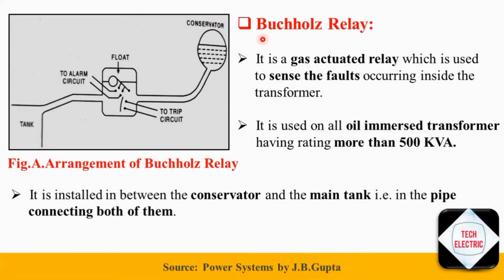Firstly, you must be thinking, what is the Buchholz relay? So Buchholz relay is a special type of gas actuated relay which is used to sense the fault occurring inside the transformer. Please note that it provides protection only against transformer internal faults and does not respond to external bushing or cable connection faults. It is used on all oil immersed transformers having rating more than 500 kVA.